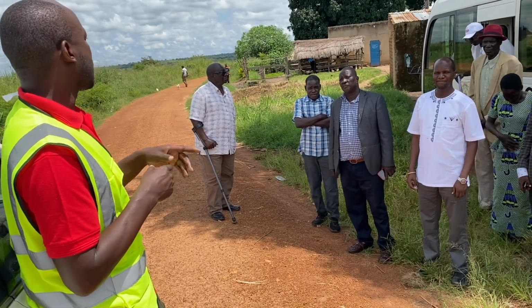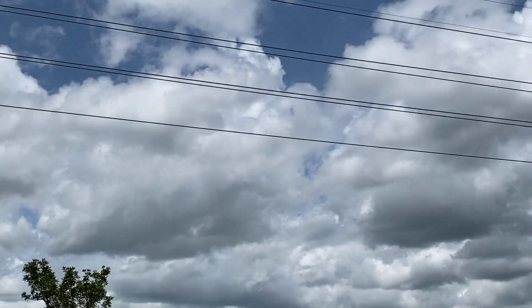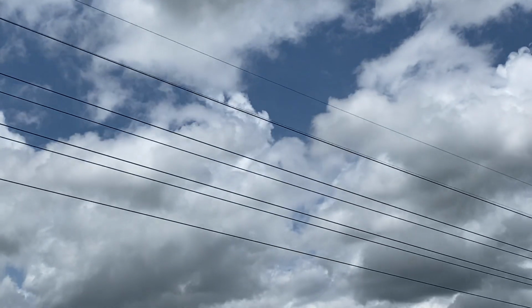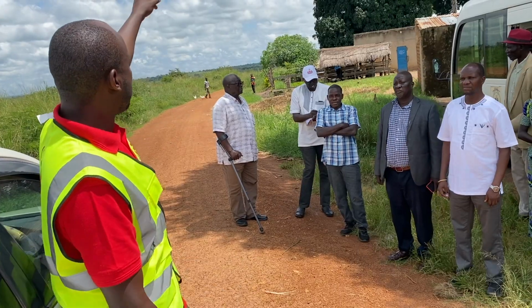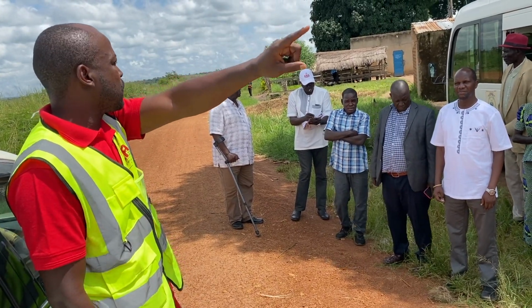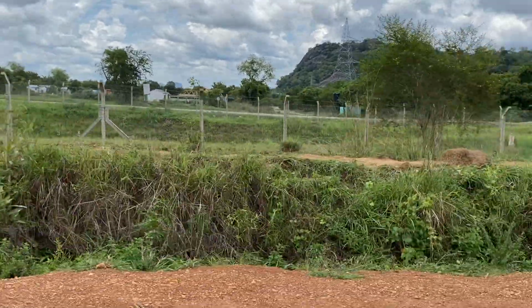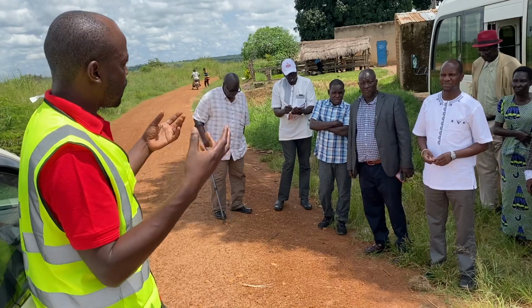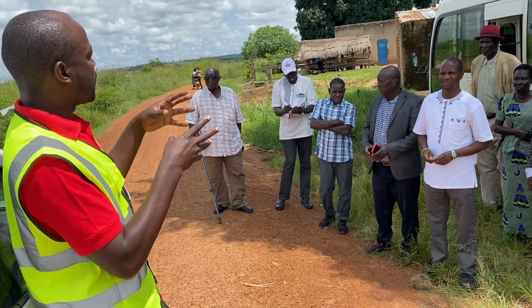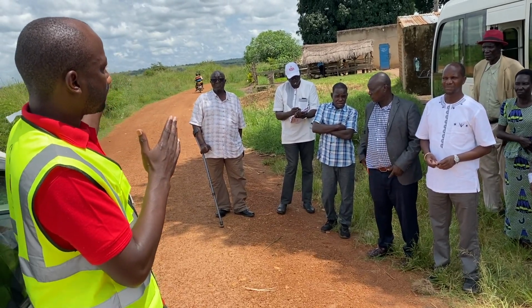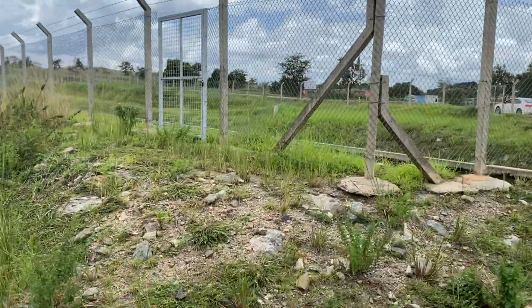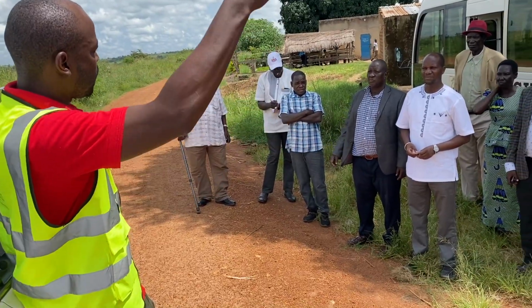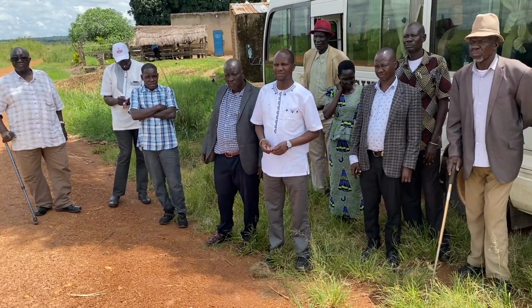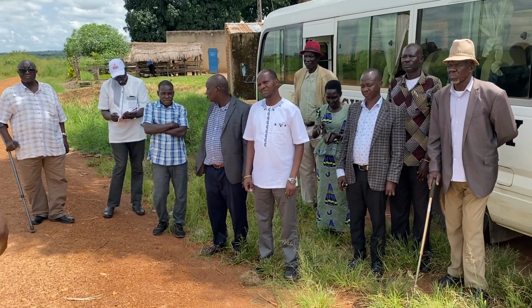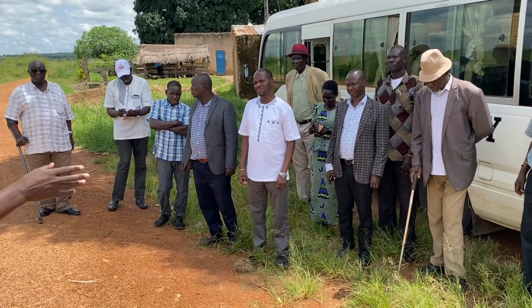Currently that power is transmitted up to Gulu substation on the line running on this side. It comes from the plant to the substation named Agago, then proceeds to Gulu substation. Gulu takes what it can use, then the balance moves towards Kole or towards Oluyo. The one going to Oluyo feeds West Nile, and the one going to Kole continues through Lira, feeding areas up to where it finishes.